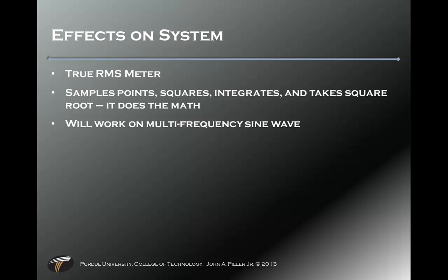A true RMS meter actually samples the waveform, squares the samples, integrates, and takes the square root — it does the math and works on multi-frequency sine waves. In fact, most meters you'll purchase today are true RMS, but you'll find out in lab the effects on average-responding and peak-responding meters.